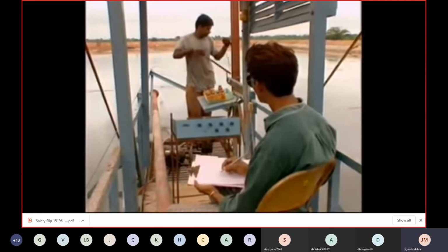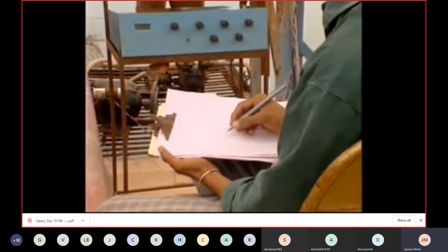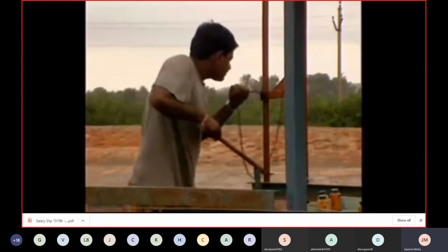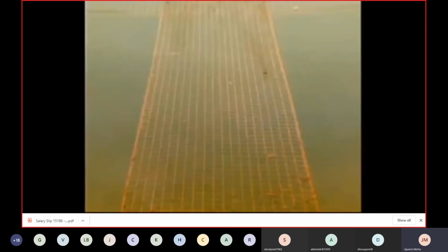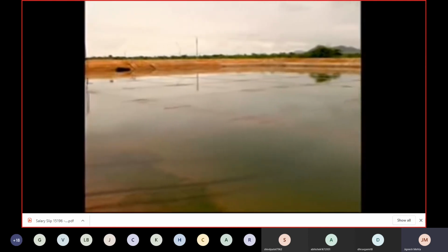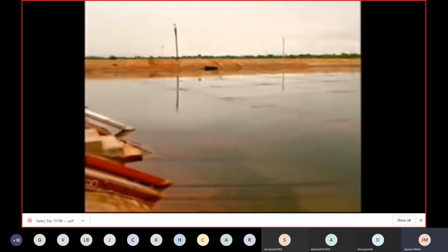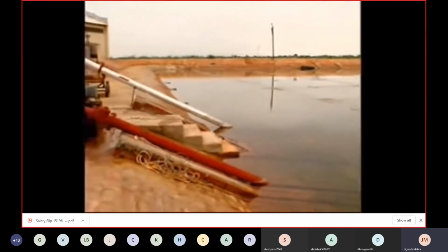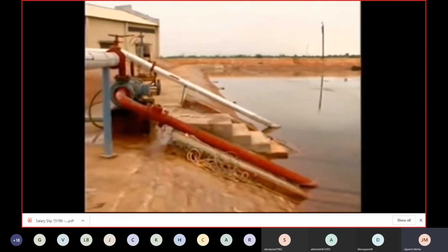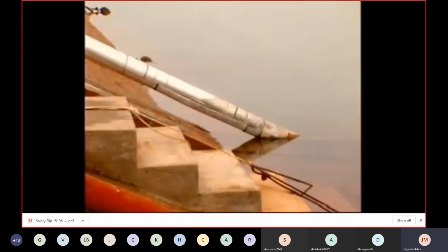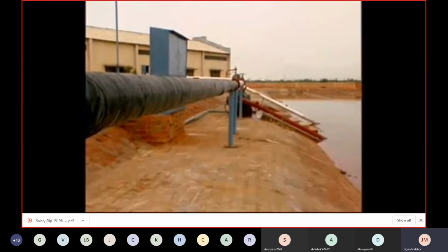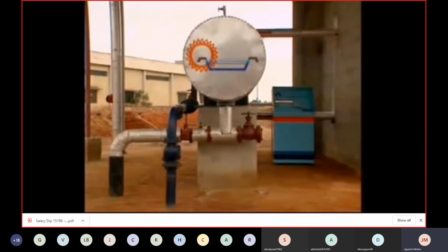Solar ponds create energy by inhibiting the natural tendency of water to become lighter and rise upwards when heated. Three salty layers of water with varying density are maintained with great care. Plastic nets control movement on the surface of the pond, and the aim is to trap heat in the heaviest layer at the bottom, made dense with large amounts of salt. Brine or hot salty water in the lowest layer is the basic source of heat in this process, which is lifted through a pipe and taken into a heat exchanger.